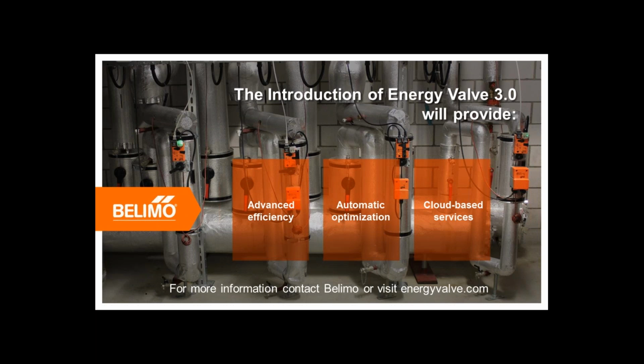Can the energy valve replace control valves of a FAHU? Yes. Okay. Can we replace the BTU meters for energy valves? Can you replace BTU meters with energy valves? Certainly. The energy valve also acts as a BTU meter. So in effect, you could replace BTU meters and a control valve with an energy valve.